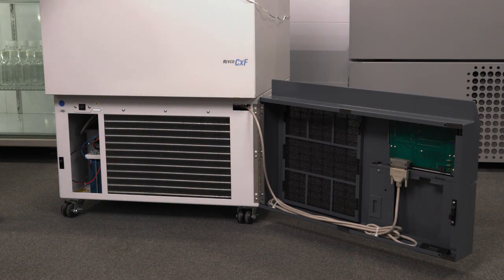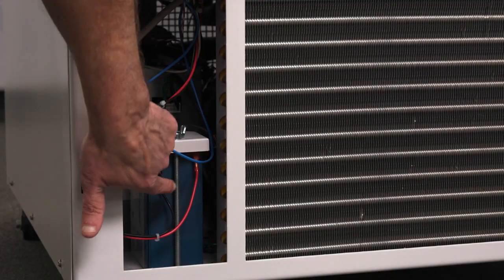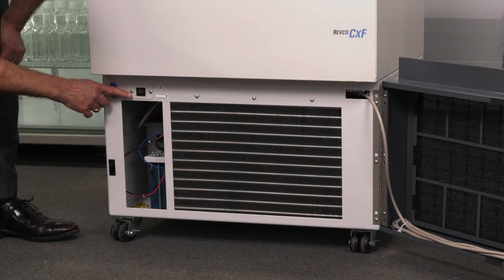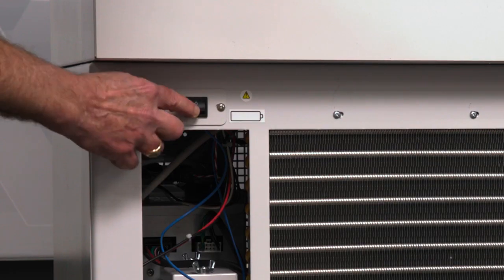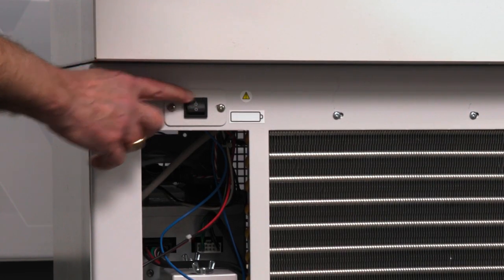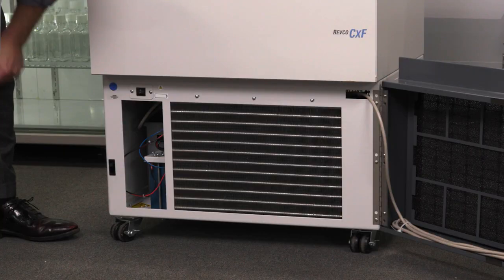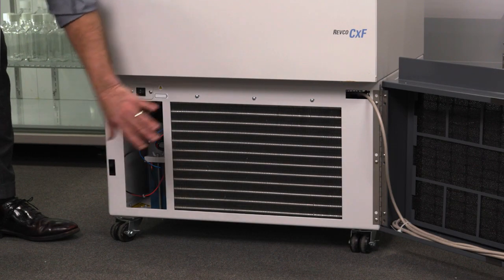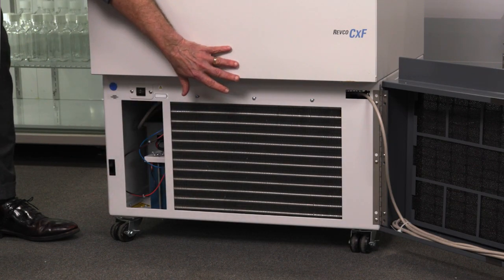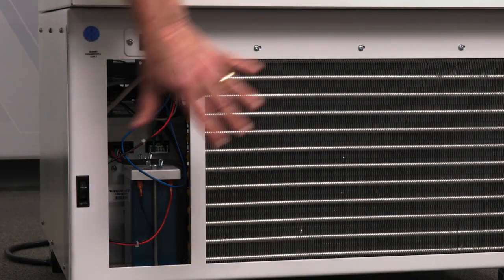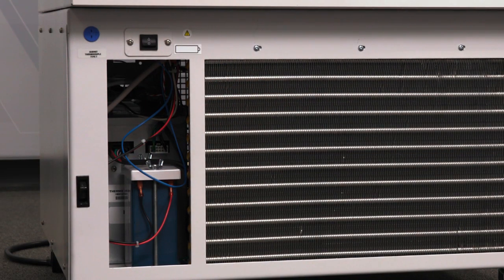The other thing I want to point out is the battery location. So the battery is here, and important to note that when the unit is shipped, that battery will be off. It'll be actually turned off. You'll turn it on as part of the startup procedure. Keep in mind, this battery will not operate the refrigeration system. It only keeps the alarms and the display operating while the battery still has charge.